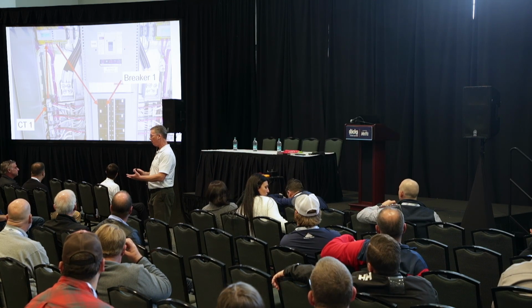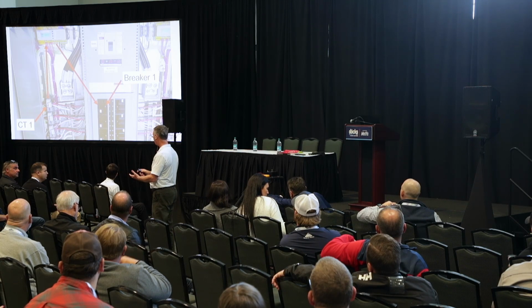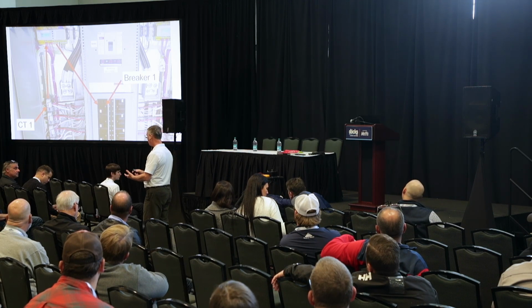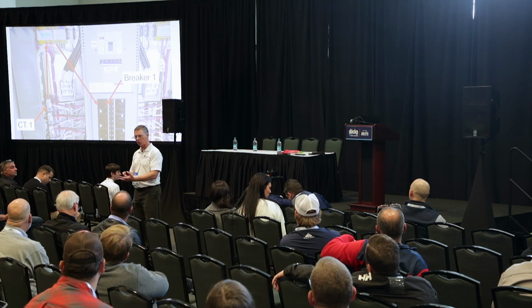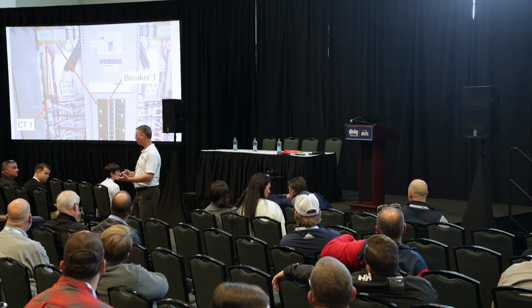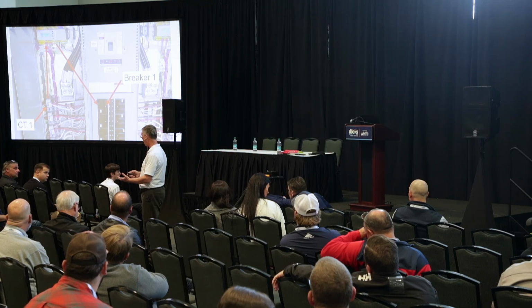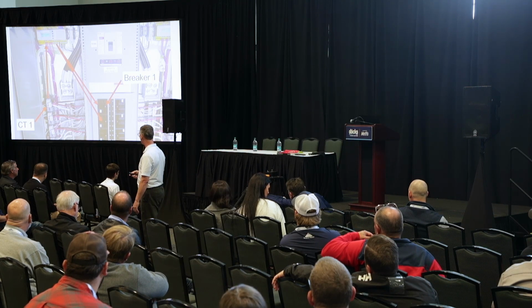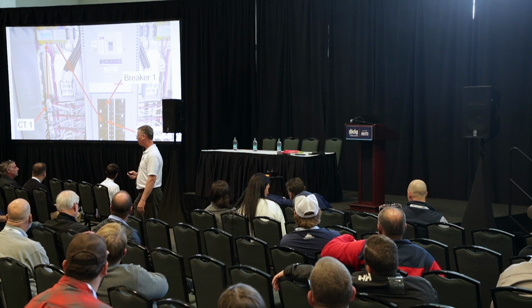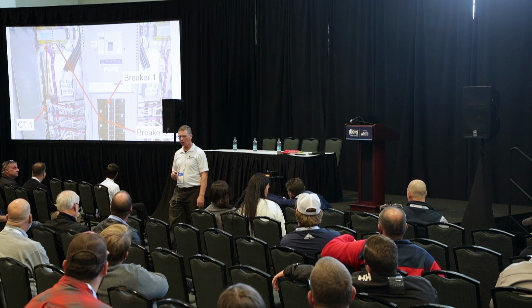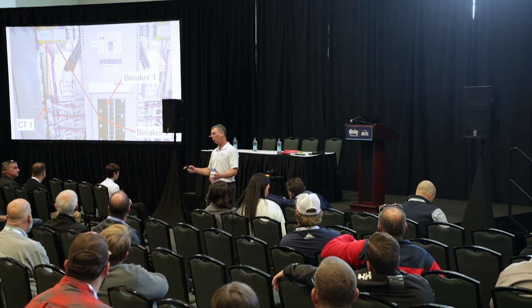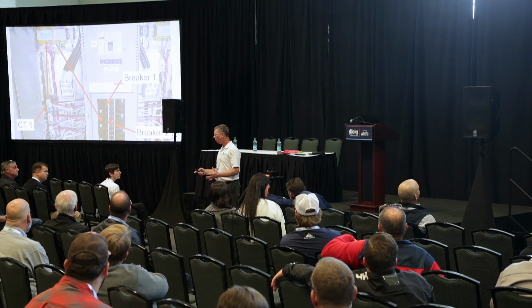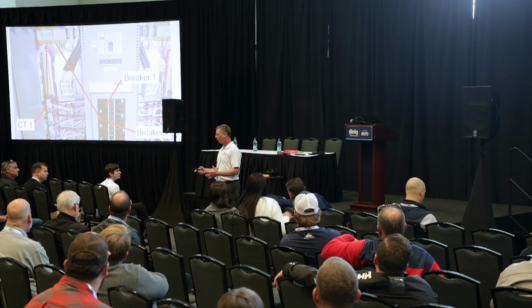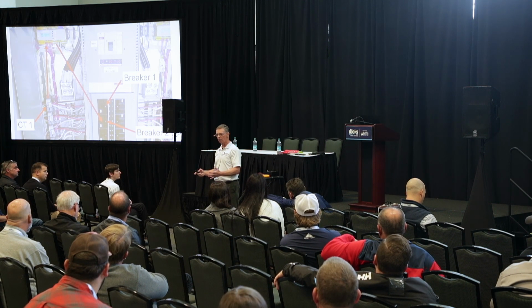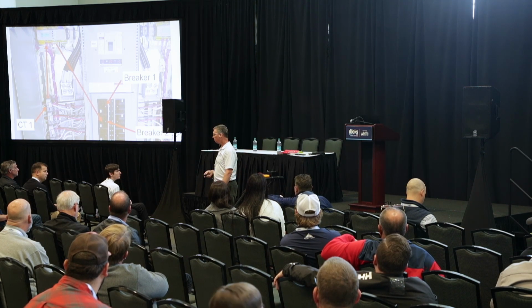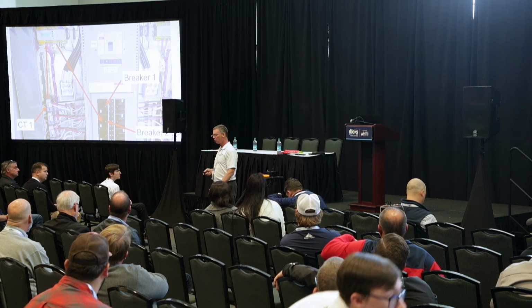Well, when I started ramping up to 100 milliamps, I heard something click, which sounded like a breaker, but the circuit was still energized. So I could leak up to 200 some odd milliamps after it already tripped. What happened, it did not trip breaker 1, but tripped breaker 2, and would not de-energize my circuit. So if I was being electrocuted on the circuit on breaker 1 and leaking 100 milliamps or more, my circuit would never get de-energized. And actually there's fatalities because of this right now, because of that miswire.